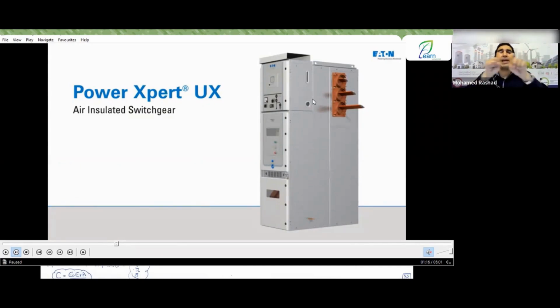These tubes contain SF6 gas, meaning you won't be able to see the bus bar. The bus bar is inside a sealed tube, connected to the breaker through another tube, and the breaker is connected to the cable through a third tube. In the end, you only see the cable coming out like this. So everything is immersed or submerged in a gas called SF6 gas, sulfur hexafluoride. This is referred to as gas insulated switchgear.